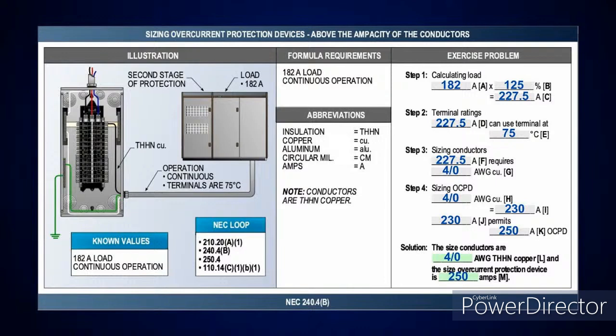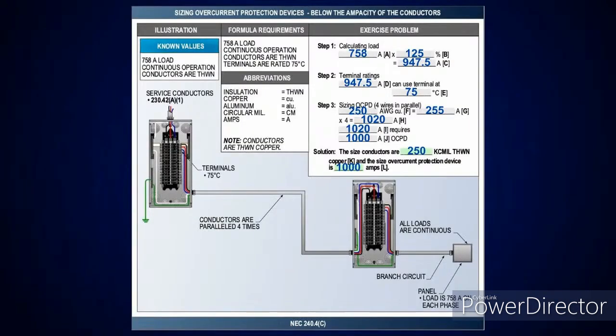But now when I get to 240.4C, I'm over 800 amps. You cannot exceed, and I'm going to show you that calculation here. It's very simple. So basically, you're saying you could protect the load or the conductor. If you're protecting the conductor, you could protect it over that ampacity rating. But if you're protecting the load, then it has to be under. That's right.